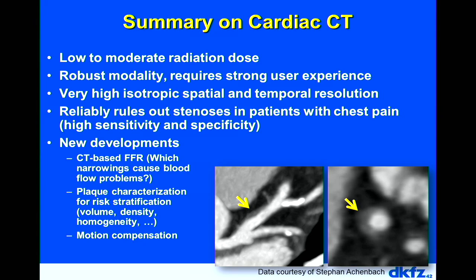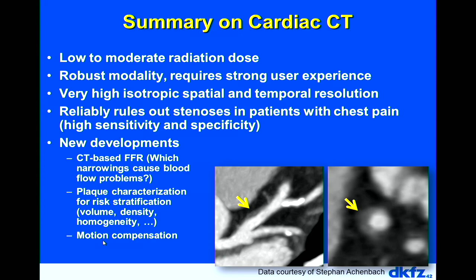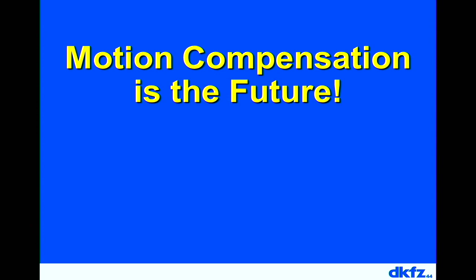One remaining challenge is motion: coronary motion is still too fast. For example, with a 250 ms rotation time, 125 ms is needed to acquire a scan; coronaries moving at 50 mm/s means 6 mm of movement during the scan — too much for sharp depiction. In 10–20% of patients, image quality problems arise from motion artifacts. The future of cardiac CT image reconstruction lies in motion compensation: finding out how the coronary artery moves and compensating for it during reconstruction.